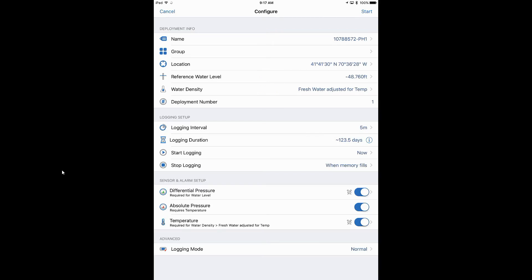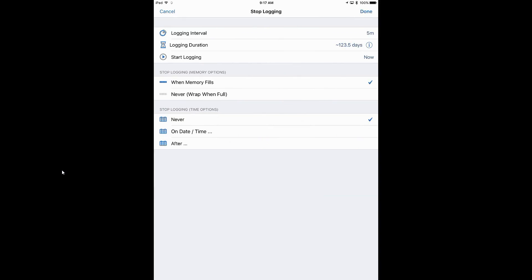Under Stop Logging, we can tell the logger what to do when the memory fills up at 123.5 days. We can tell it to stop logging when memory fills, or we can select Never, which means it will wrap — also called circular logging or first-in-first-out logging. When memory fills, it will begin to overwrite the old data with new data. You can also configure it to stop at a specific time and date or after a specific time period, such as two weeks.